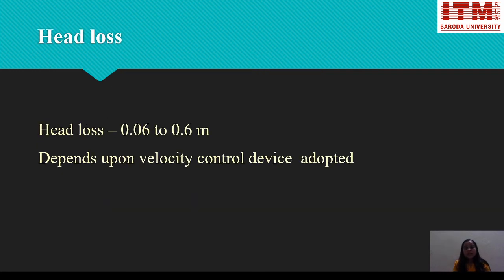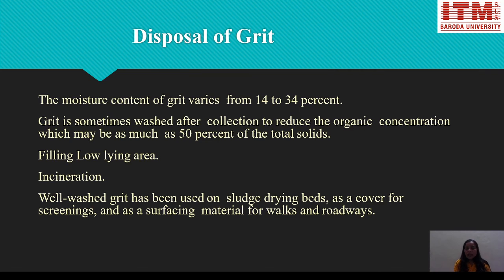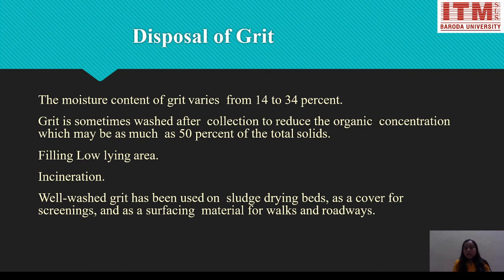Head loss should be 0.06 to 0.6 meters, depending on the velocity control device. Grit collected at the bottom has a moisture content of 14 to 34%. Grit is sometimes washed after collection to reduce organic concentration, which may be as much as 50% of total solids. Disposal options include filling in low-lying areas, incineration at high temperature in a closed tank, or using washed grit as cover material over screenings at a dumping site.